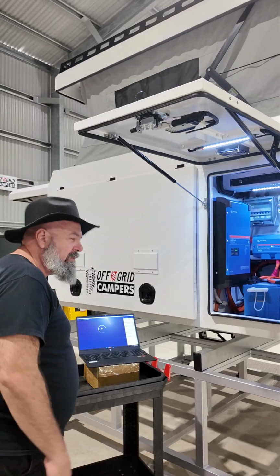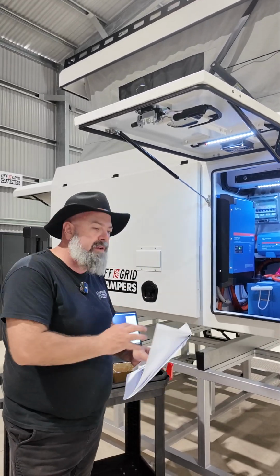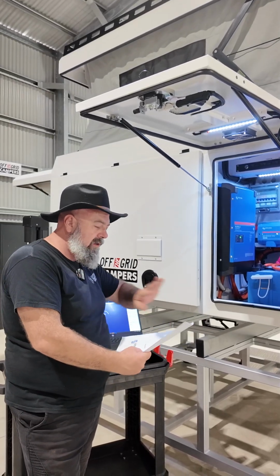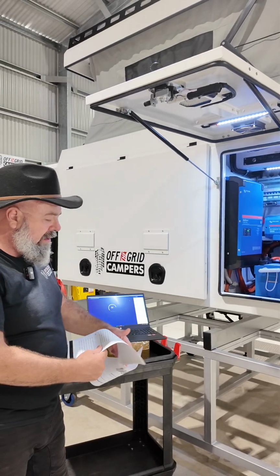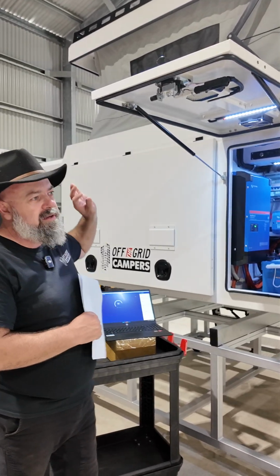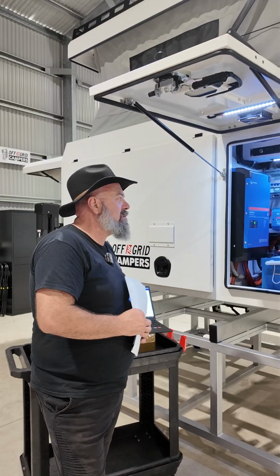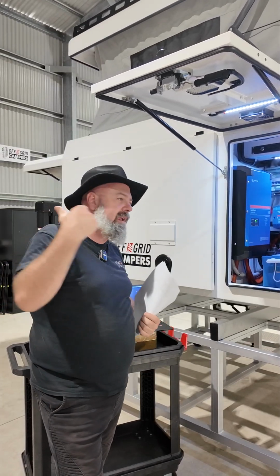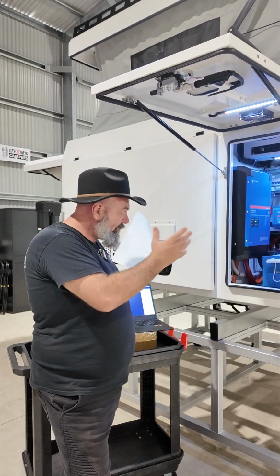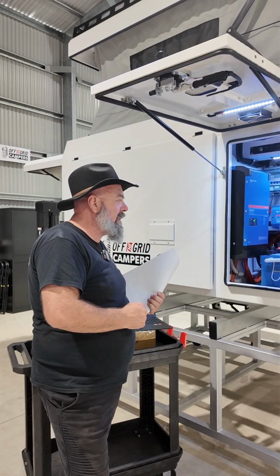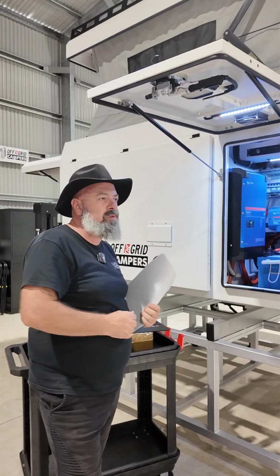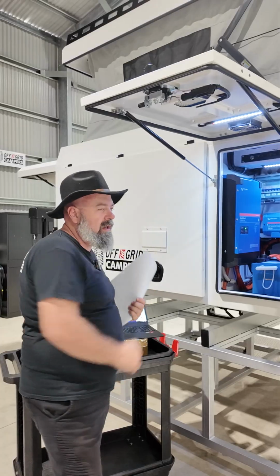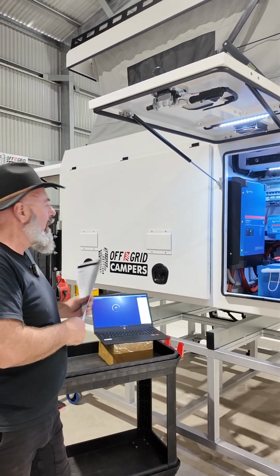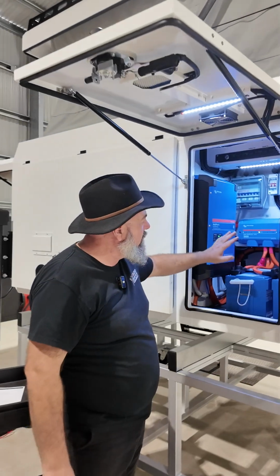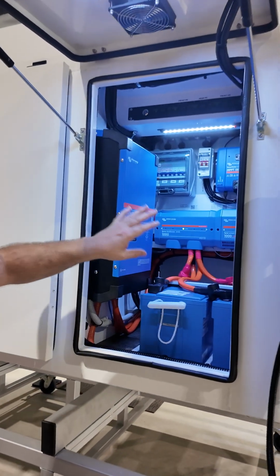We have a guide we've written to make sure we don't miss any steps, and we test everything, following a systematic procedure, from programming the touchscreen on the other side, because it talks to all the components in the system, relaying state of charge, temperatures, and all the telemetry and data through the comms cables. There's a loom of cables that runs back to the Cerbo on the other side - we'll walk around there in a minute. All these devices need to be programmed individually, and we do that.